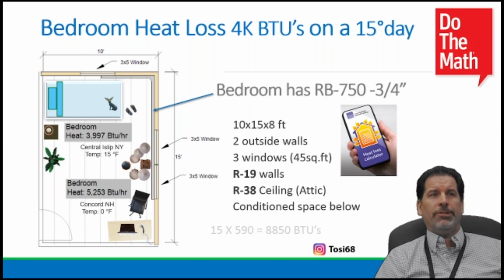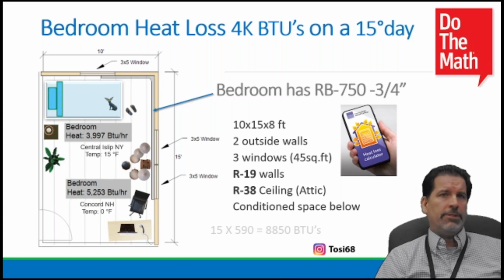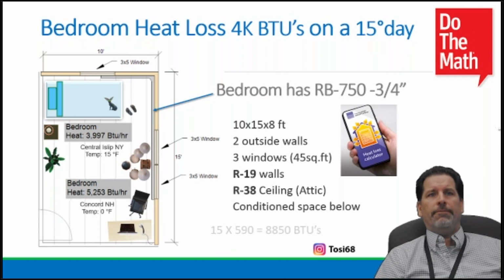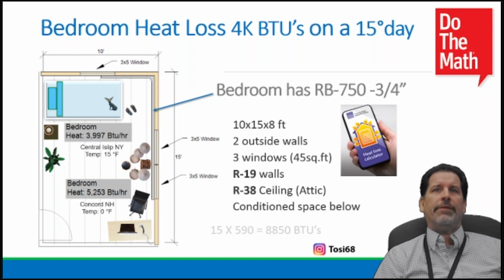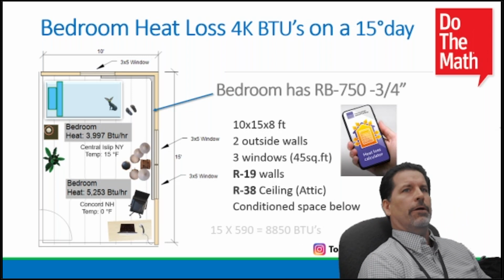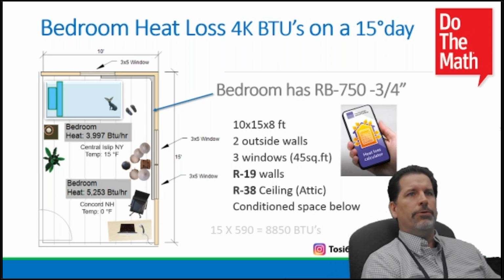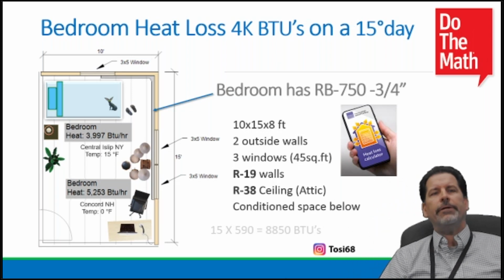If this same room was up in Concord, New Hampshire, their design day is 0. And you can see now the BTUs that were calculated for the same size room, same application, all the R values, was just under 5,300. Well, if that room has 15 feet of baseboard there, right? RB 750 3/4. How many BTUs do you think we are actually delivering?